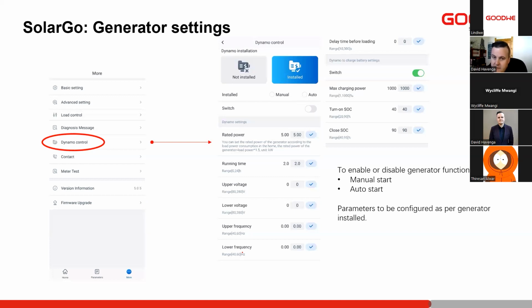So if you only want to use the generator, make sure your loads are off and you're going to manually start to just charge the batteries. That's fine. Yeah, you can select the generator's rated power, which means the inverter will only consume that maximum power. You can also switch it from auto or manual, so manually turn it on or automatically turn it on. So when it's on manual, you can put the switch to say switch generator on.